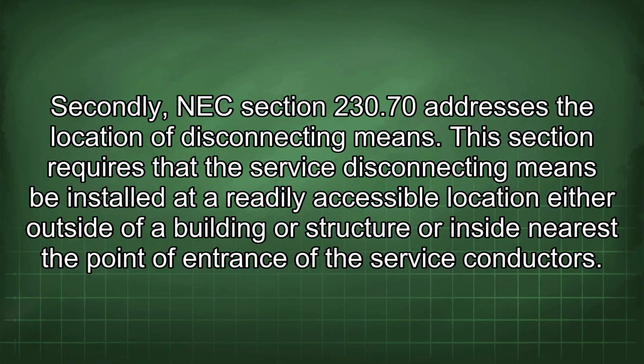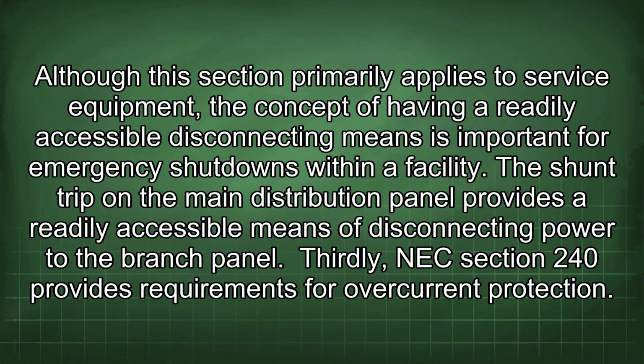Secondly, NEC Section 230.70 addresses the location of disconnecting means. This section requires that the service disconnecting means be installed at a readily accessible location either outside of a building or structure or inside nearest the point of entrance of the service conductors. Although this section primarily applies to service equipment, the concept of having a readily accessible disconnecting means is important for emergency shutdowns within a facility. The shunt trip on the main distribution panel provides a readily accessible means of disconnecting power to the branch panel.